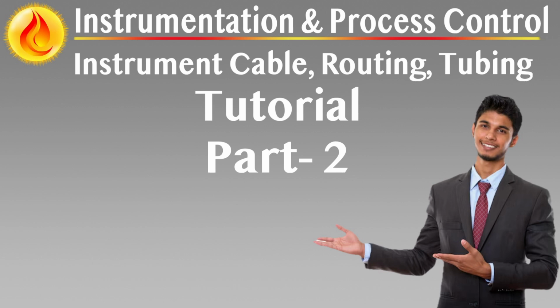Cable gland specification for environmental sealing and EMC compliance. Cable glands serve multiple critical functions: securing cable entries, maintaining enclosure ingress protection, preserving explosion protection ratings, and enabling reliable EMC bonding. For all electric signal cables entering field instruments or junction boxes, metallic glands must be used. These glands must provide circumferential 360-degree, low-impedance contact to connect the cable's armor or braid to the housing, effectively grounding and shielding against EMI.